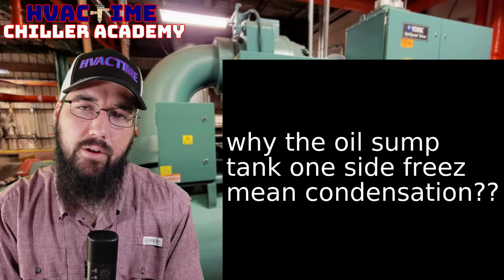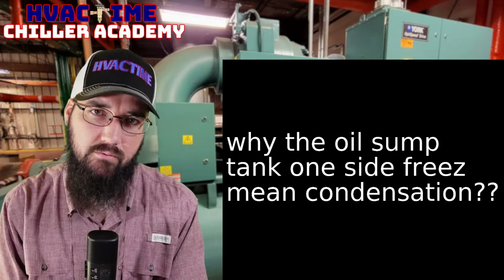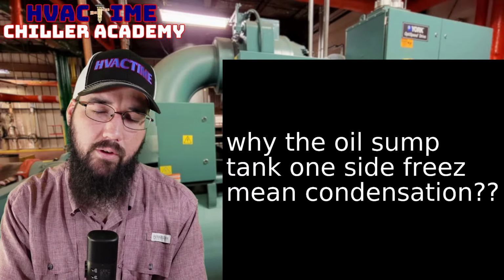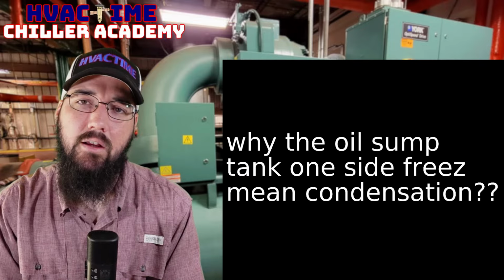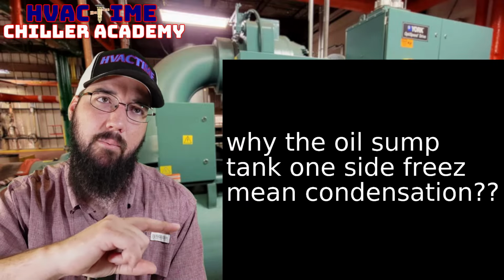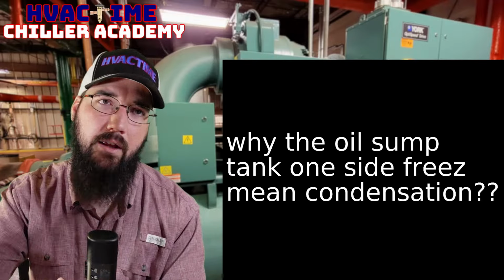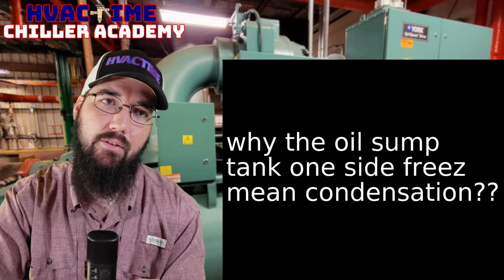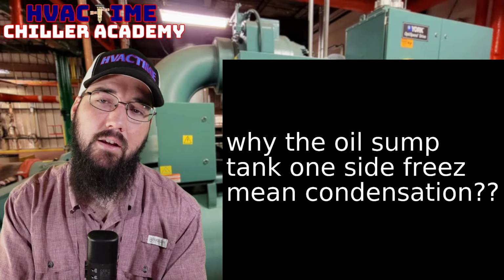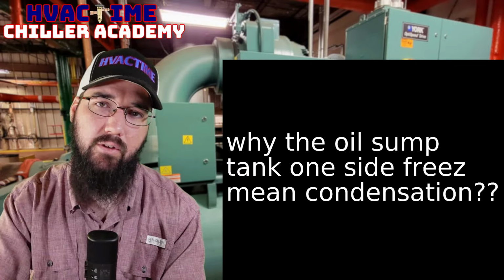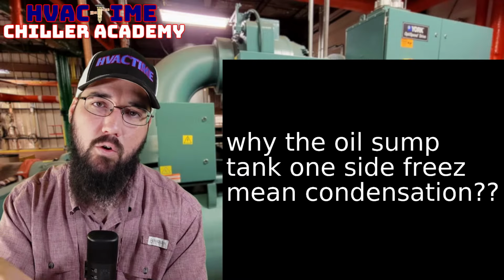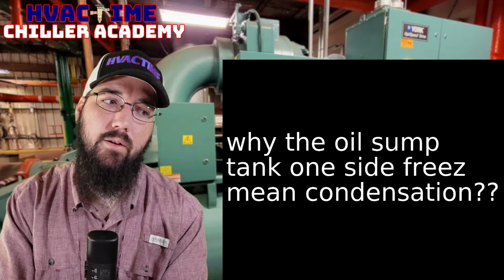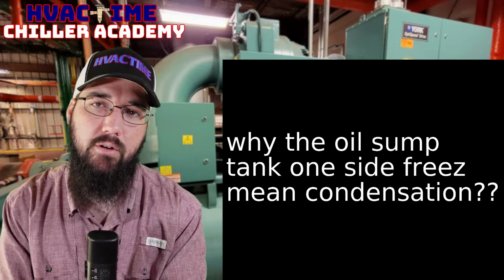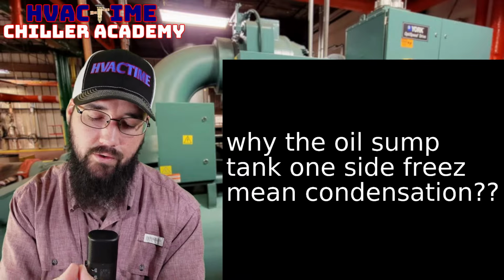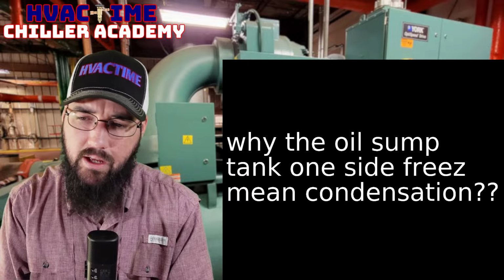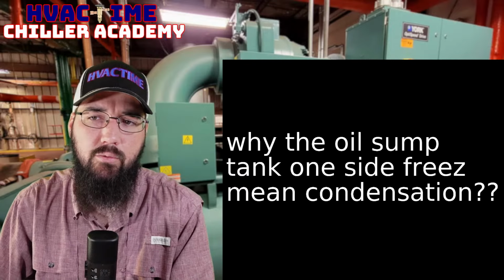Then it energizes the solenoid for the eductor and opens the line up, and we start allowing oil return from there, right? So if you're working with a YK system, that's why you're going to see that on the sump. There are two other lines on the YKs: the drain line coming out the bottom of the compressor, and a vent line tying into the suction eye of the compressor, which is meant to draw any refrigerant vapors back out of the oil. It keeps our oil sump at a lower pressure compared to the evaporator, right? So we want that oil sump to be our lowest pressure point in the system to keep that oil there. Anyway, those don't have valves on them. If we're discussing a different machine, I'll just need a little more clarification on that.